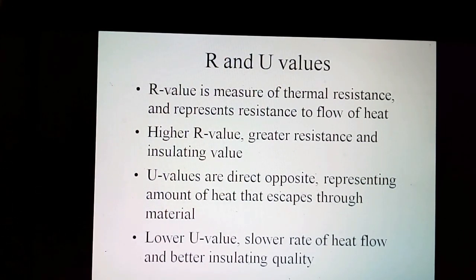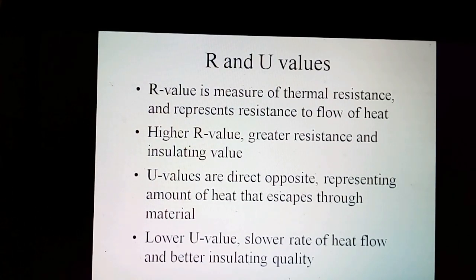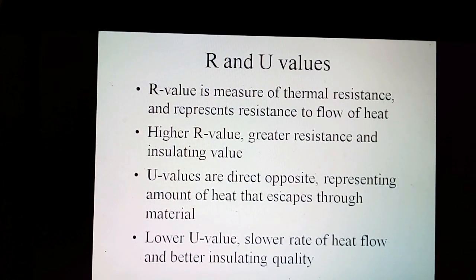The lower the U-value, the slower the rate of heat flow and the better the insulating quality. It is expressed as the thickness of the material divided by the thermal conductivity. For the thermal resistance of an entire section of material, instead of the unit resistance, divide the unit thermal resistance by the area of the material. If you have the unit thermal resistance for a wall, divide it by the cross-sectional area to compute the total resistance.